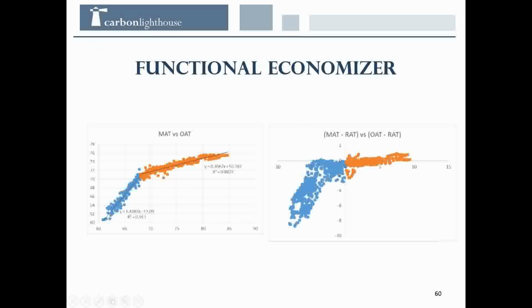Let's go back one. Is this. You should see a big kink. So you can see on the blue side of the graph, you're getting a lot more outside air, and on the orange side of the graph, you're going down to minimum position, which in this case is about 30% outside air, which in fact is a little bit high. You should be closer to usually 20% or 15% is common. So either this particular air handler needed to provide more fresh air than normal to the building occupants, or there's some leaking dampers, which is pretty common. In San Francisco, it's not really worth the extra $1,000 to fix dampers to go from 30% to 20%.